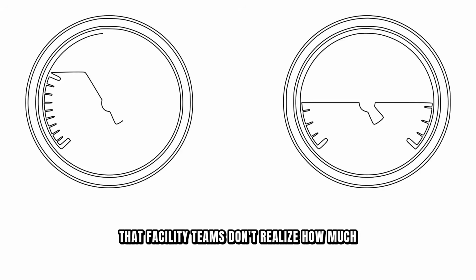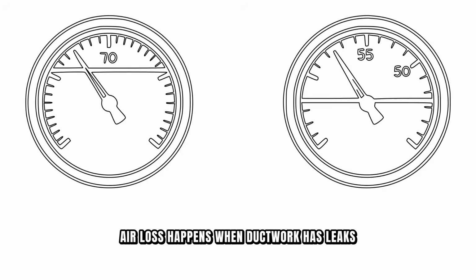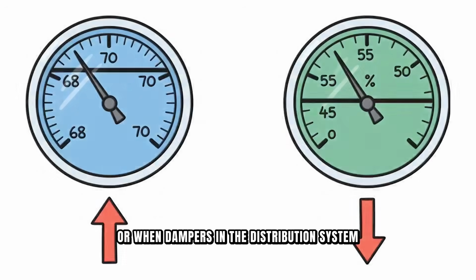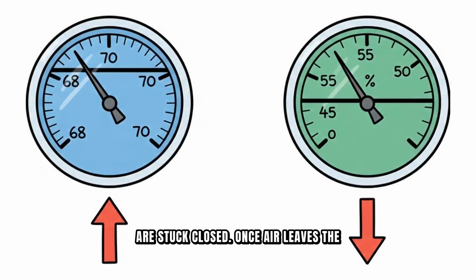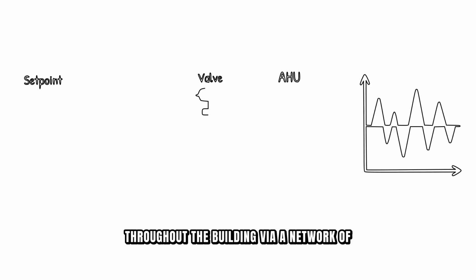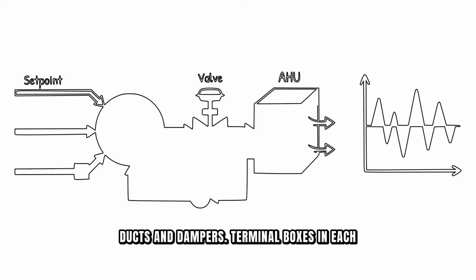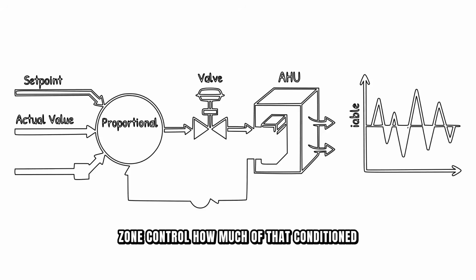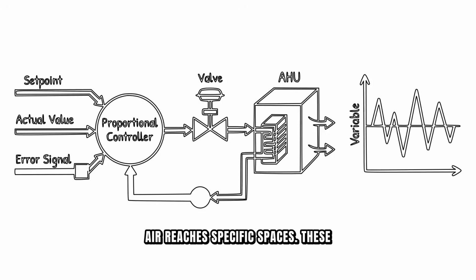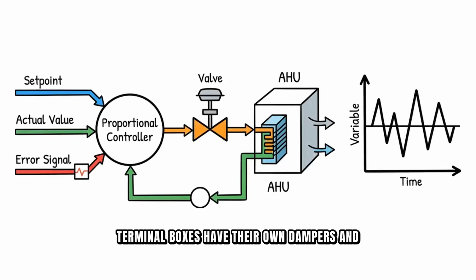We often find that facility teams don't realize how much air loss happens when ductwork has leaks or when dampers in the distribution system are stuck closed. Once air leaves the AHU through the discharge ductwork, it's distributed throughout the building via a network of ducts and dampers. Terminal boxes in each zone control how much of that conditioned air reaches specific spaces. These terminal boxes have their own dampers and sometimes heating or cooling coils for zone-level adjustment.